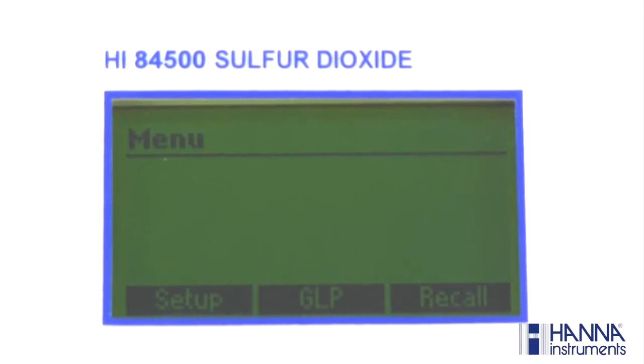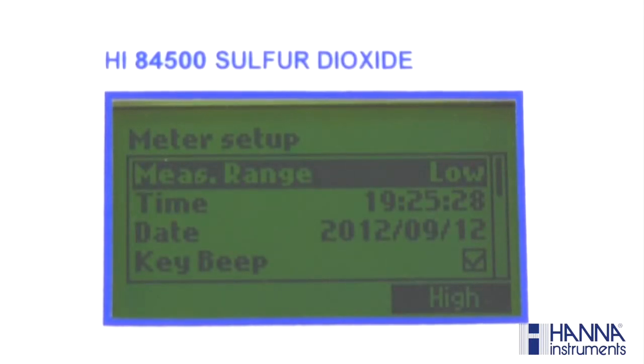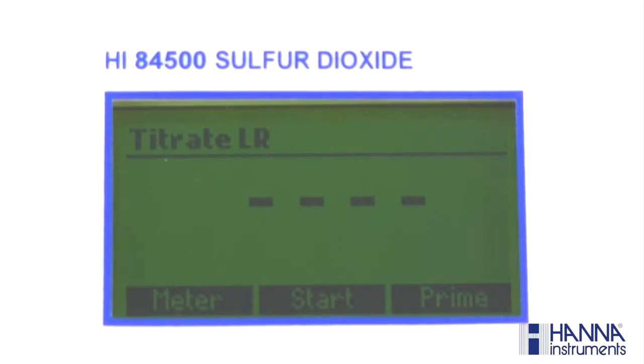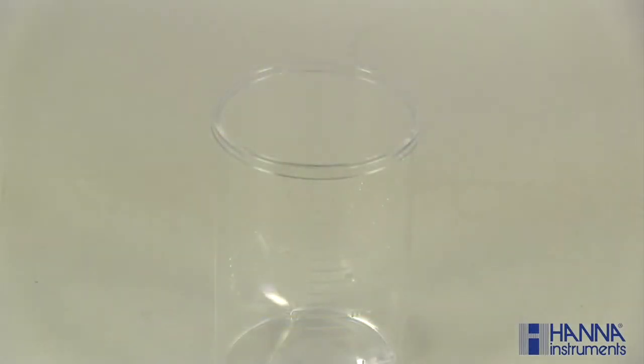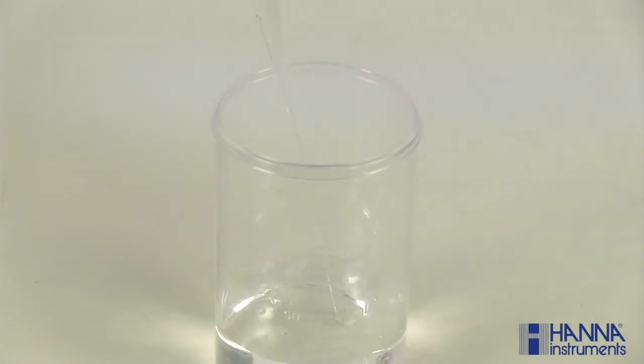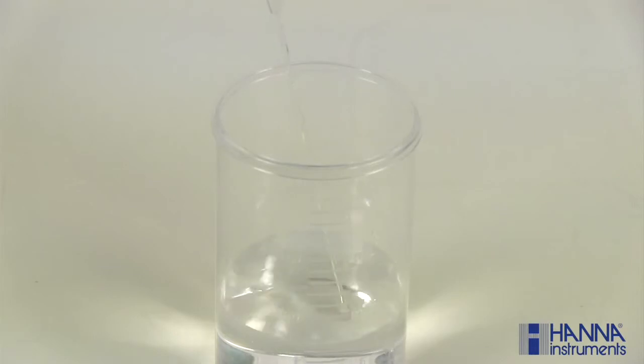Press Menu and select Setup to choose your range. We'll be measuring low-range free sulfur dioxide today. Again, you want to make sure that you have the correct titrant and that you've primed with the correct titrant as well. Using a clean pipette, precisely add 1 ml of HI-84500-55 calibration standard to a clean 100 milliliter beaker. Fill the beaker up to the 50 milliliter mark with DI water.